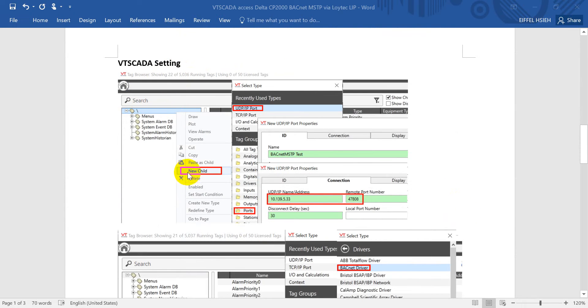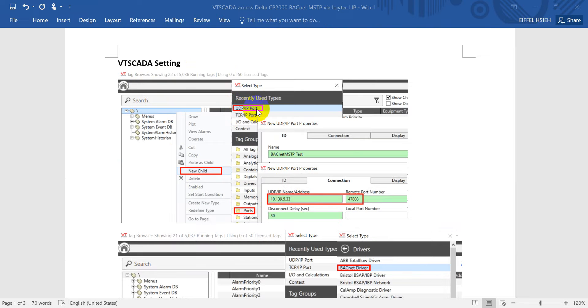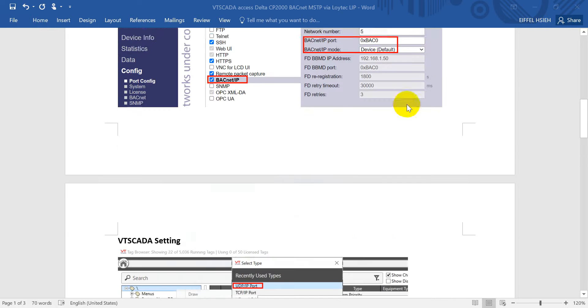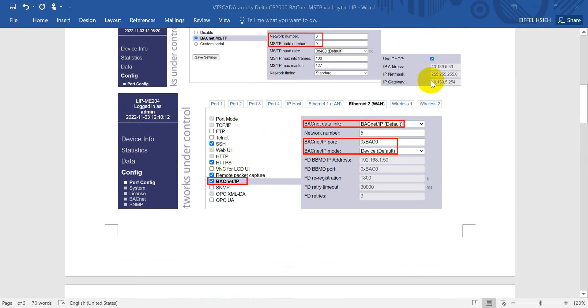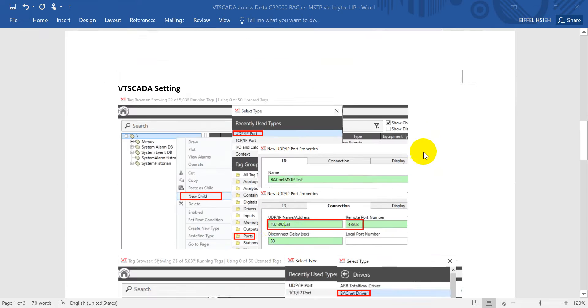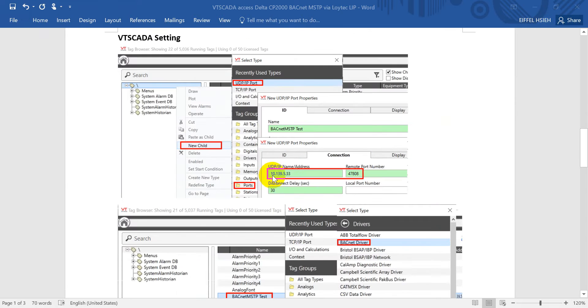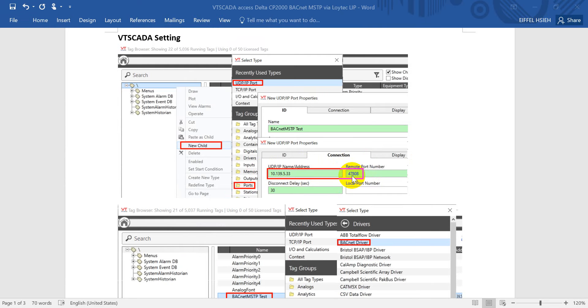After that we'll go to the VT SCADA settings. Here we click New Child, then select the port. If you've used it before, you can use the UDP IP port. Then assign the IP address we just mentioned: 10.139.5.33, and assign the BACnet default port number 47808.